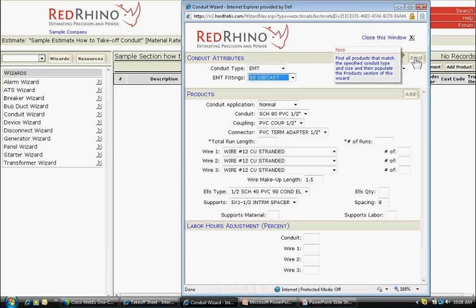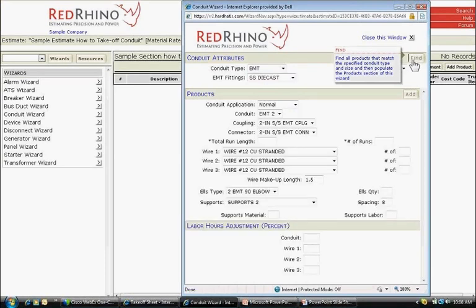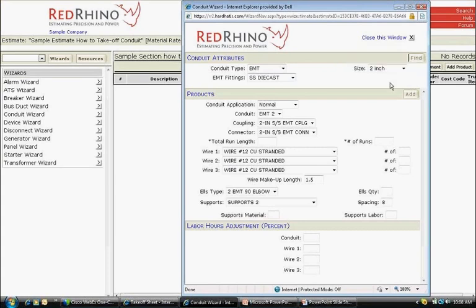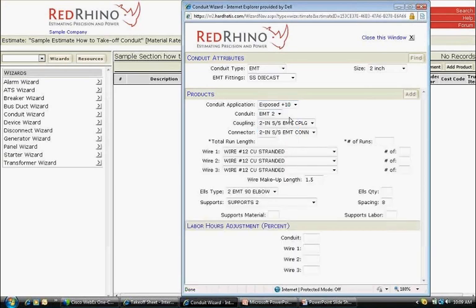Next at the top right-hand side of the pop-up window, we click the Find button. Always click the Find after finishing selections at the top. That populates the correct material down below products. As discussed earlier, the term Conduit Application refers to conduit levels of difficulty. I click the Conduit Application drop-down. Now Red Rhino has several conduit applications. Each application has different labor quantities depending on the difficulty of installation. As shown on the takeoff sheet, I set the application at plus 10 feet, like the conduit is to be installed above 10 feet off the floor.